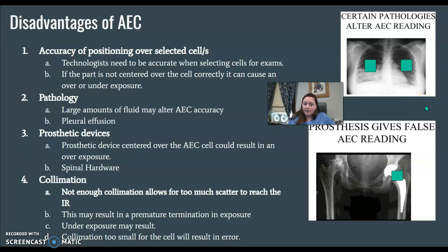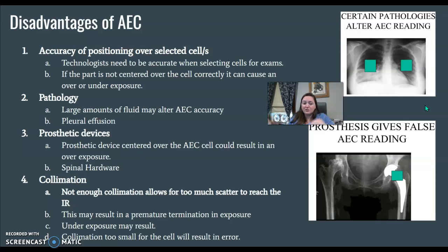Collimation can also cause an error. If you don't collimate and your field is wide open, it's going to allow too much scatter to reach the image receptor. Those ionization chambers are going to fill faster the more open the light field you use. Collimation is something simple we can do to improve our image, reduce scatter, reduce patient dose, and make sure AEC works properly.